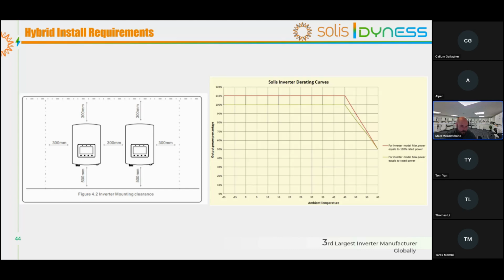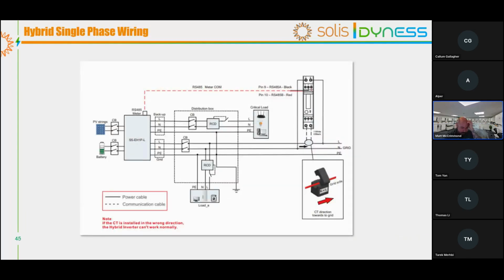Ultimately, the distances are between another inverter or a solid wall, for example. If it's trunking, then it's not an issue, but a solid surface can bounce the heat back or have a negative impact on how much air gets around the inverter. So we're talking mainly about other inverters and walls. This is what these limitations are. On the right-hand side, you can also see the derating curve based on temperature. As it gets closer to 60 degrees, you can lose almost 50% of your rated output. That's massive for your customer, so please consider that as you're doing it.